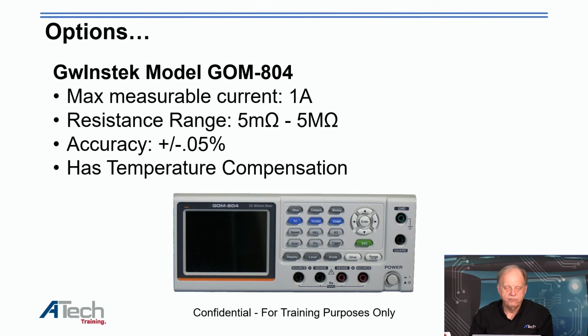We've got some purchasing options at different price ranges. This is the GW Instek, model GOM 804, which we have on the bench here. It has a measured current value of 1 amp, and a resistance range of 5 milliohms up to 5 megohms, which is a pretty good range. The accuracy is 0.05, which is really good compared to some of the other meters we've discussed. It also has temperature compensation.